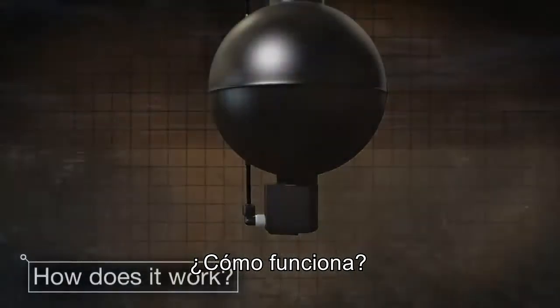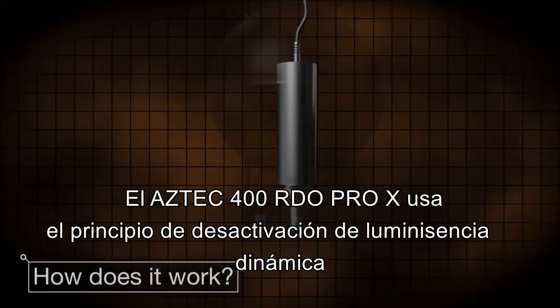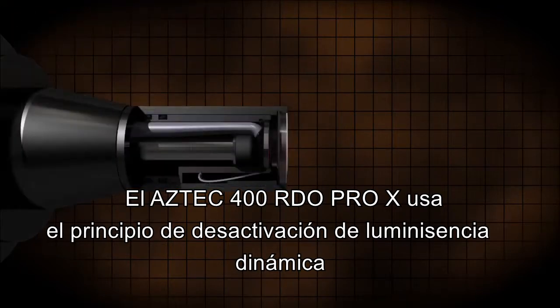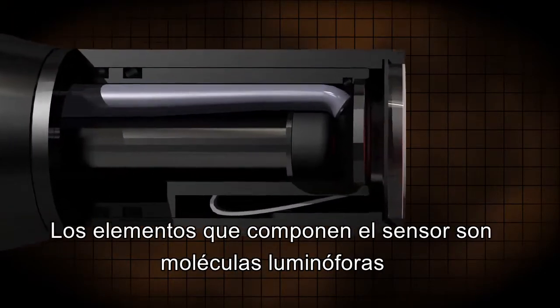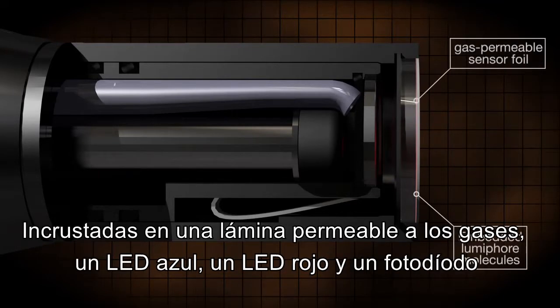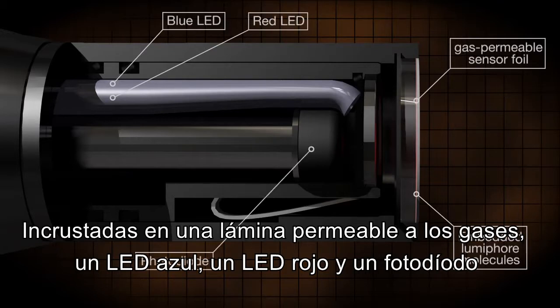How does it work? The Aztec 400 RDO Pro X uses the dynamic luminescence quenching principle. The sensor's construction features lumiphore molecules embedded in a gas permeable sensing foil element, a blue LED, a red LED, and photodiode.